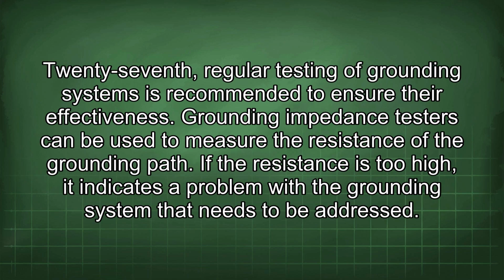27th. Regular testing of grounding systems is recommended to ensure their effectiveness. Grounding impedance testers can be used to measure the resistance of the grounding path. If the resistance is too high, it indicates a problem with the grounding system that needs to be addressed.